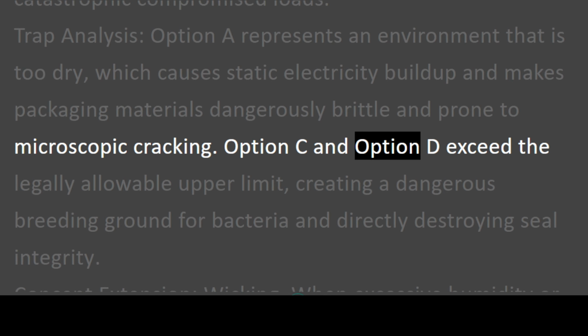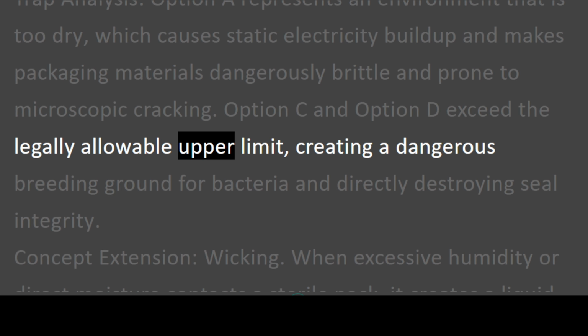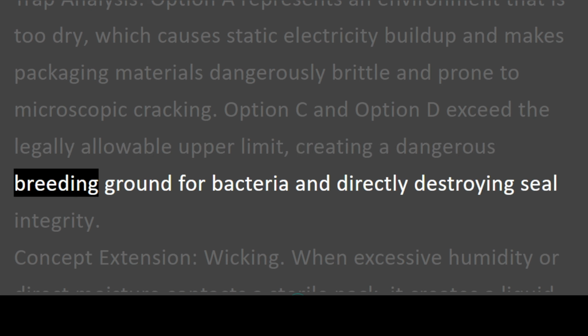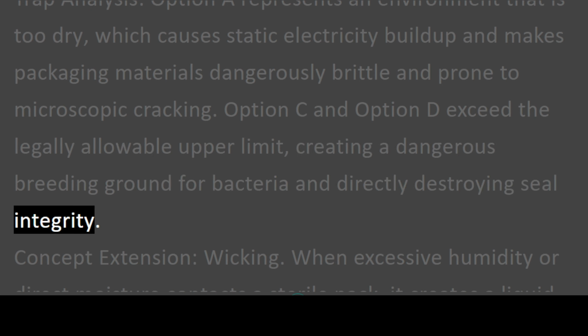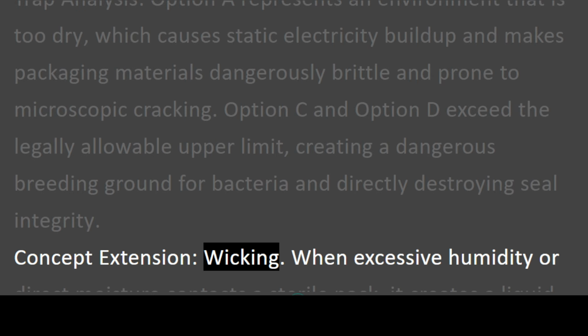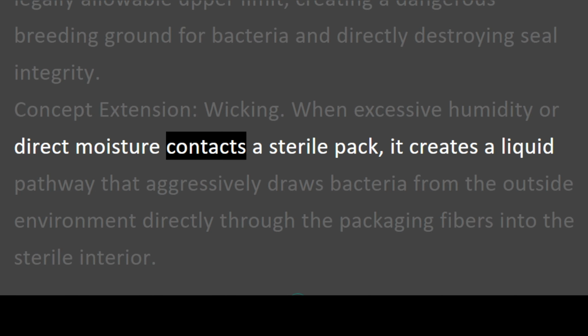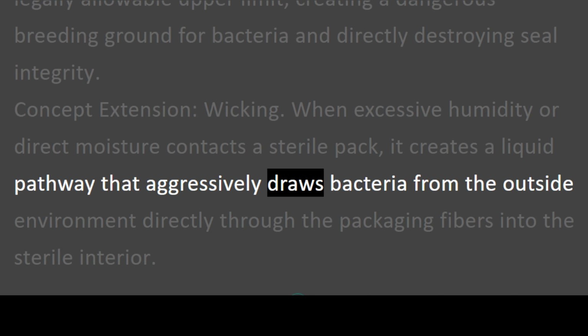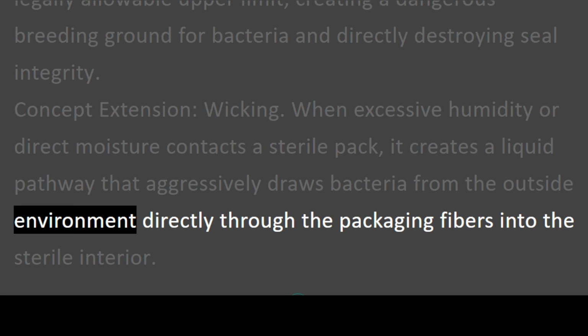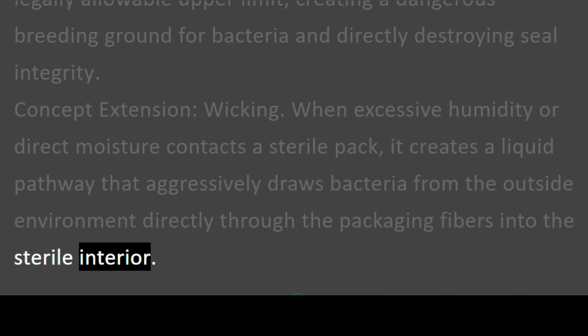Option C and Option D exceed the legally allowable upper limit, creating a dangerous breeding ground for bacteria and directly destroying seal integrity. Concept extension, wicking. When excessive humidity or direct moisture contacts a sterile pack, it creates a liquid pathway that aggressively draws bacteria from the outside environment directly through the packaging fibers into the sterile interior.